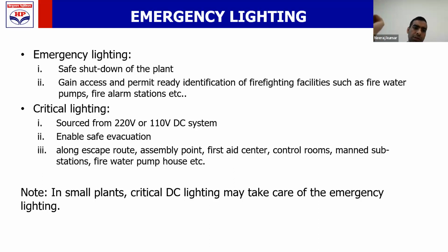In addition to emergency light, DC critical lights shall also be provided. The purpose of DC critical light is evacuation of people in case of emergency. So at which locations should you provide these critical lights? You are making it for evacuation.